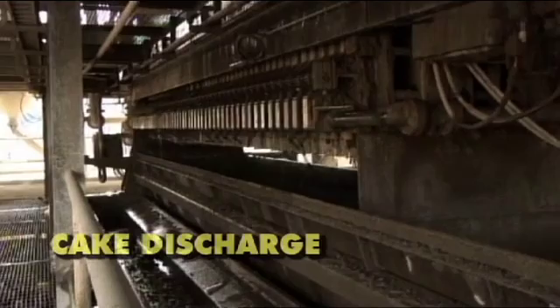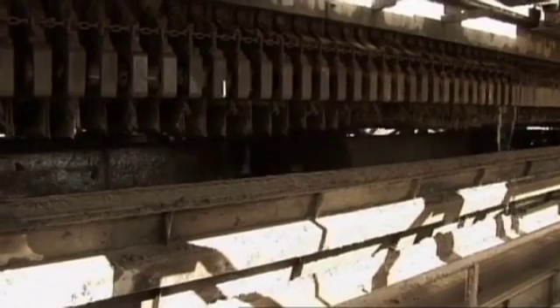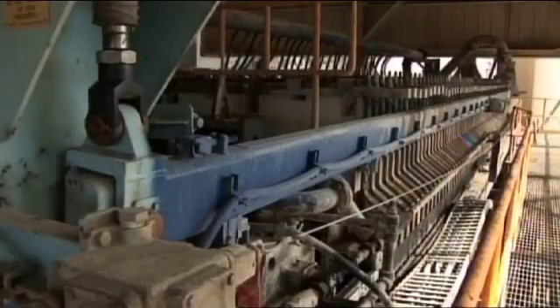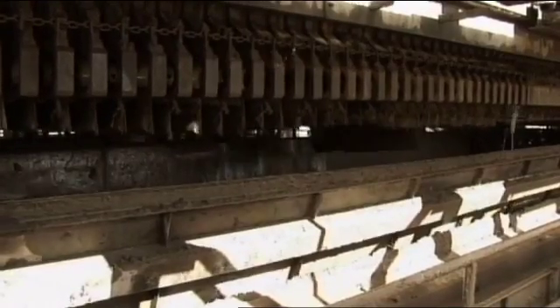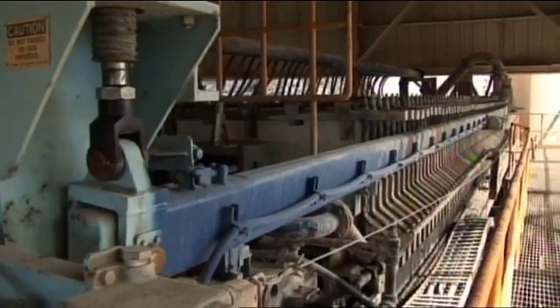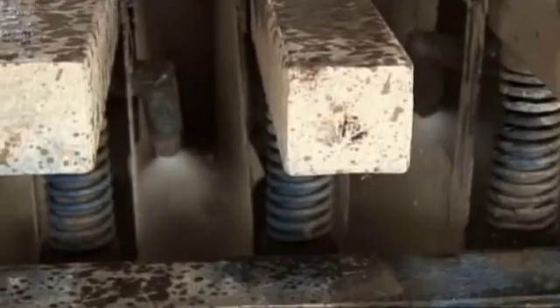Filter cakes are released by their own weight. Additionally, with spring-loaded filter cloth support bars, if filter cakes stay momentarily within the chamber, an automatic detector activates vibration bars to complete the discharge cycle. Drip trays then close and the cloth wash sequence efficiently washes all of the filter cloths at once, ending the cycle.